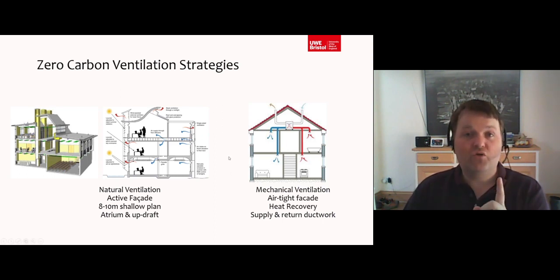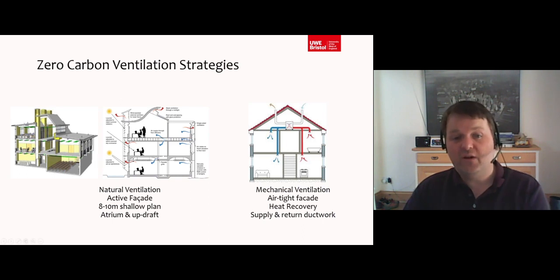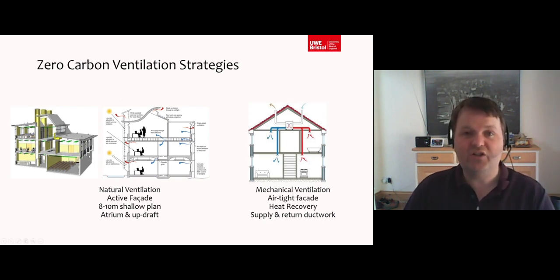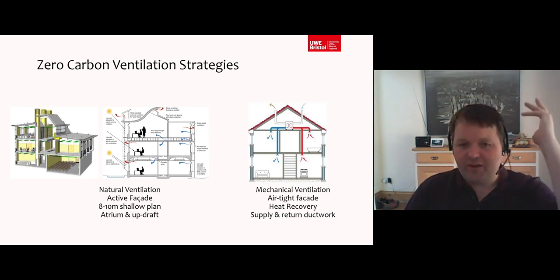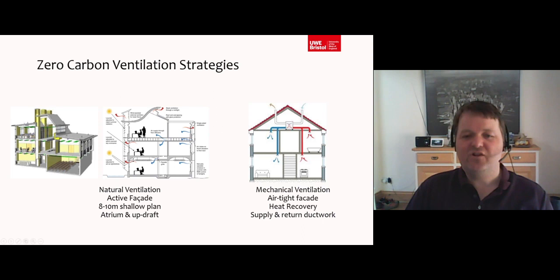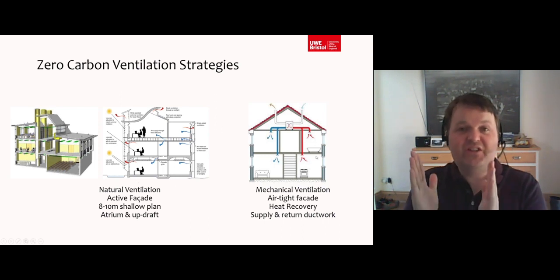There is a major drawback in that we are assuming the air outside here is clean enough. The air quality is clean enough. They say that only about 30% of London could even consider natural ventilation because of air quality issues. And so we have to look around our building and see is there going to be pollution from cars or noise or smell from something nearby whereby natural ventilation is not a good strategy. And in that case, we go to the other strategy, the sealed box strategy.